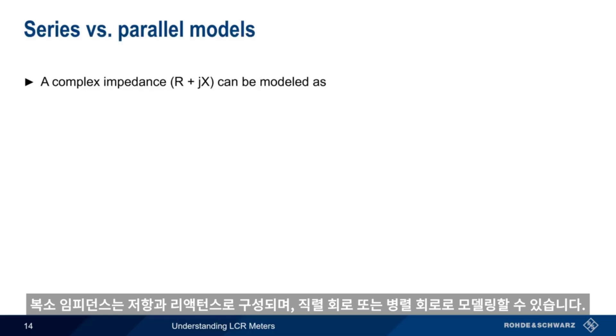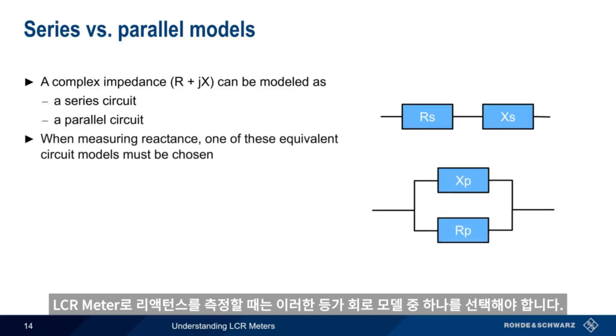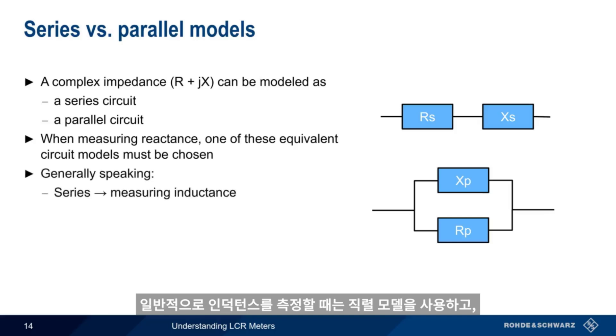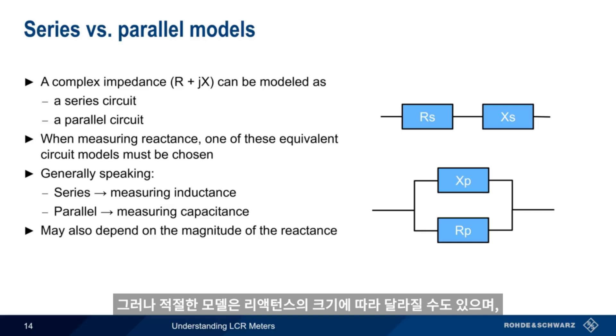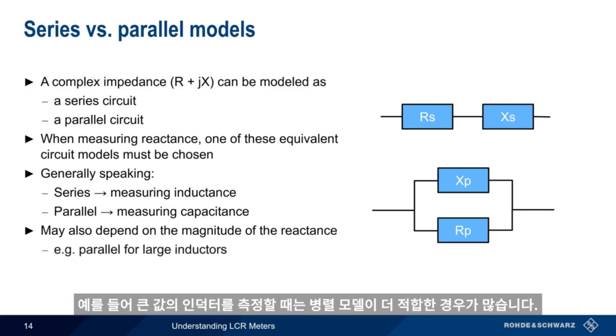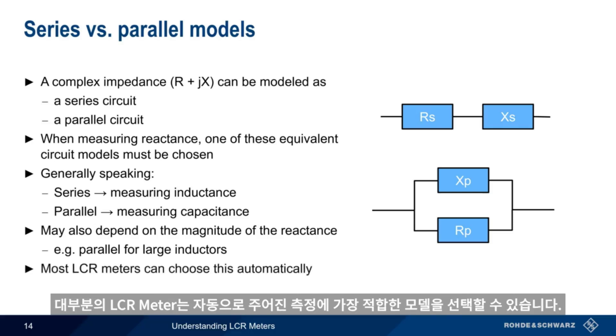Complex impedances consist of a resistance and a reactance, and these can be modeled either as a series circuit or as a parallel circuit. When measuring reactance with an LCR meter, one of these equivalent circuit models must be chosen. Generally speaking, the series model is used when measuring inductance, and the parallel model is used when measuring capacitance. However, the appropriate model may also depend on the magnitude of the reactance — for example, when measuring large inductors, the parallel model is often more appropriate. Most LCR meters will automatically choose the most appropriate model for a given measurement.